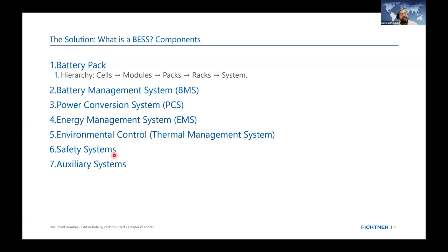The 6th one is safety systems, such as on-site safety like HVAC—heating, ventilation, and air conditioning. We also take care of fire suppression. If there is a thermal runaway, it should not propagate to another cell or module within 5 minutes, per IEC standards. So I need to design the system so it does not propagate. The battery manufacturers and BESS manufacturers will follow that.